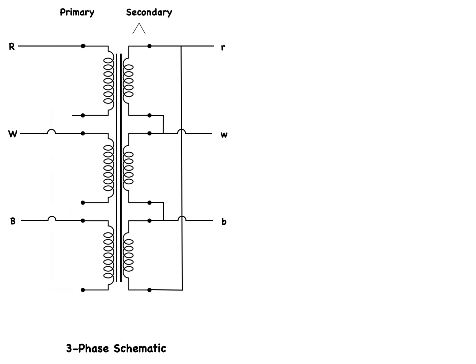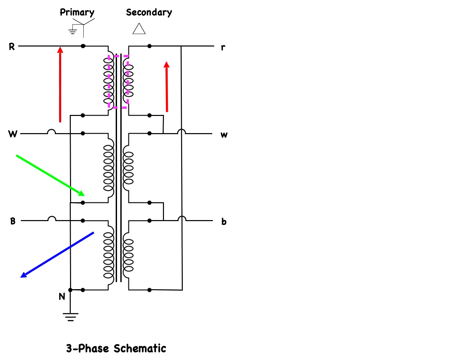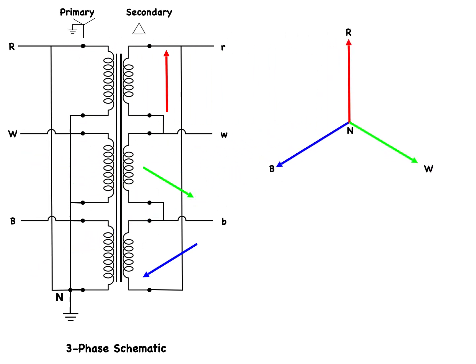Let's leave the secondary connected as delta and reconnect the primary in a grounded Y. The primary is now connected again to a balanced three-phase system — red, white, and blue. Remember that each transformer's secondary winding is magnetically linked to the primary; therefore the open-circuit secondary voltages are in phase with the primary voltages. As before, the primary voltage phasors are connected together and form a neutral. The secondary winding of the primary red-to-neutral winding is connected between the red and white phase of the secondary, and because it is in phase with the primary red-to-neutral voltage, we can label it as secondary phase-to-phase red-to-white voltage.